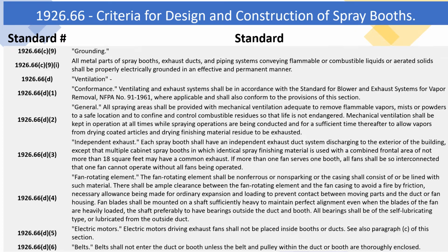1926.66(d)(3) Independent exhaust. Each spray booth shall have an independent exhaust duct system discharging to the exterior of the building, except that multiple cabinet spray booths in which identical spray finishing material is used with a combined frontal area of not more than 18 square feet may have a common exhaust. If more than one fan serves one booth, all fans shall be so interconnected that one fan cannot operate without all fans being operated.